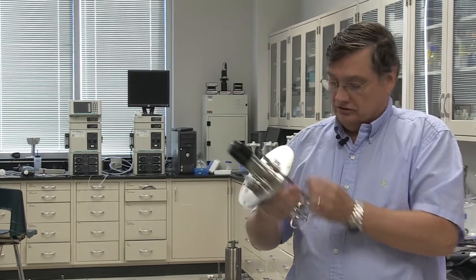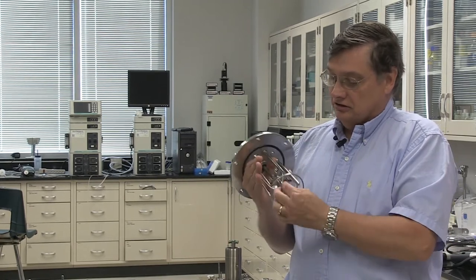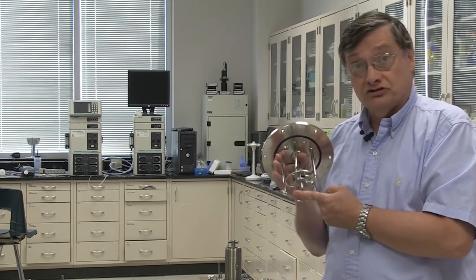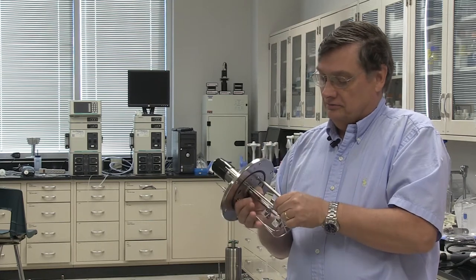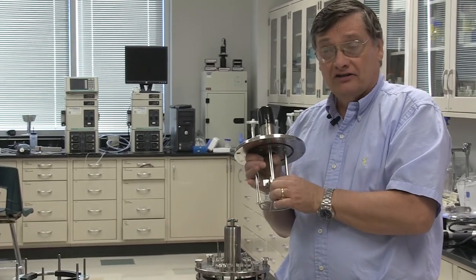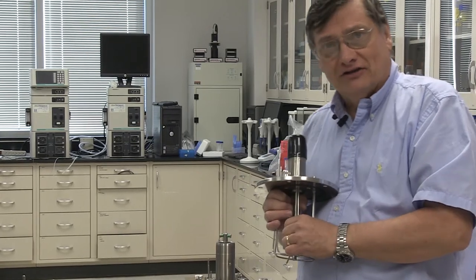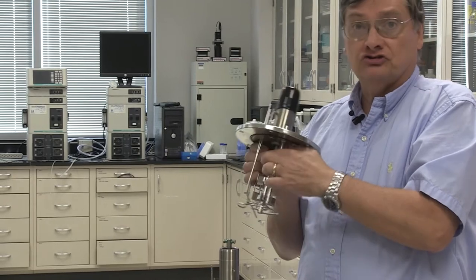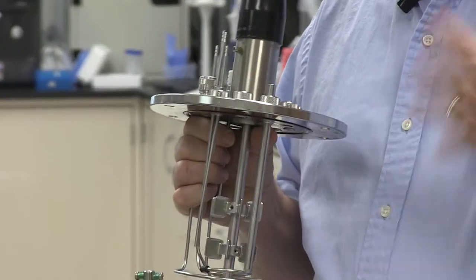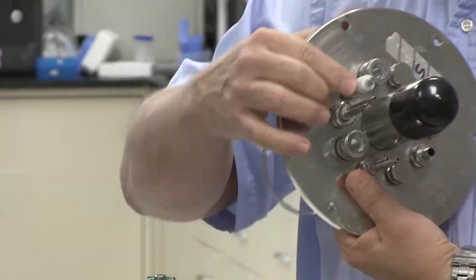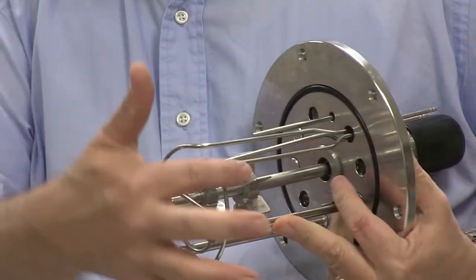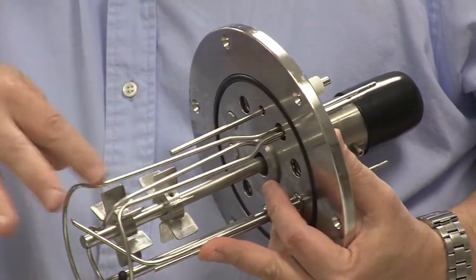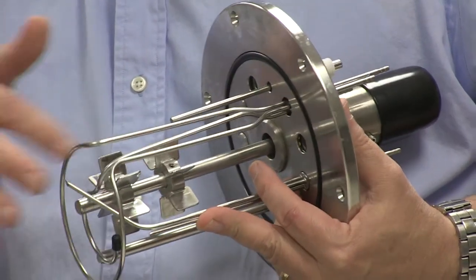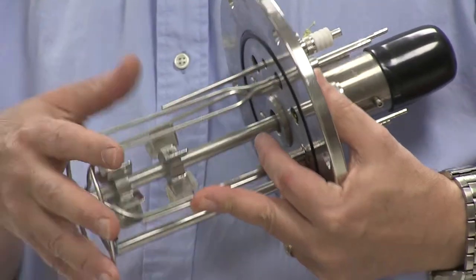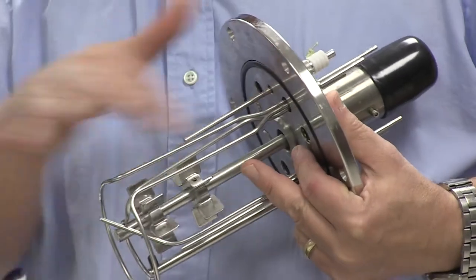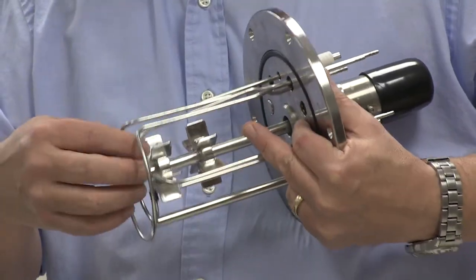We have this triport here that has the harvest tube, which is a tube that goes to the very bottom of the vessel, which is used in harvesting. We have a sample tube, which goes about halfway down the vessel, which is used if you want to collect a sample. And we'll be talking later about the sampling apparatus, which mounts onto here. And then there's a short, just auxiliary tube that could be used for any other additions that you may want to make. The other triport on this side controls this loop here. That's a continuous loop, comes in, goes around it. That's a cooling coil. That's where cooling water comes through if the vessel gets too warm and it calls for cooling, then a solenoid allows water to percolate or circulate through it. And then the third part of the triport is what we call the sparger.